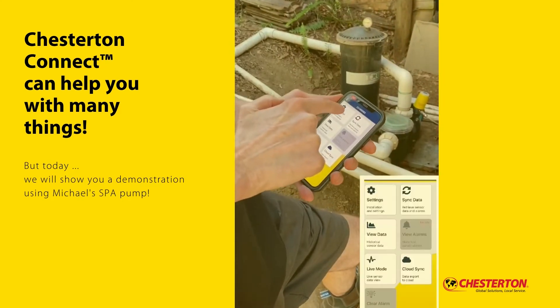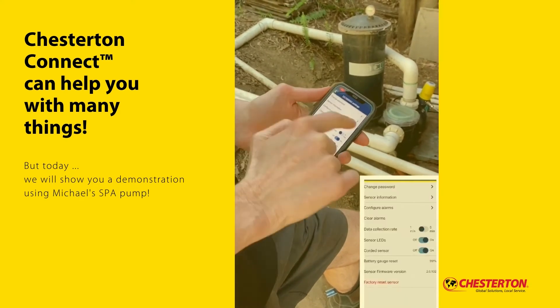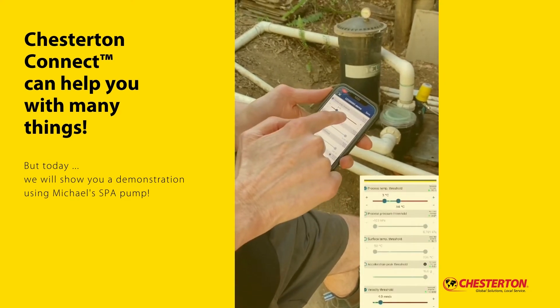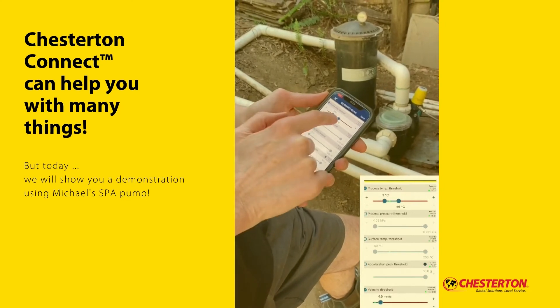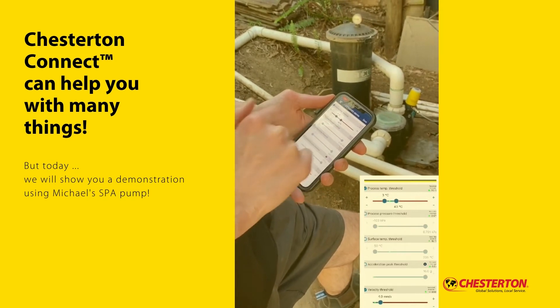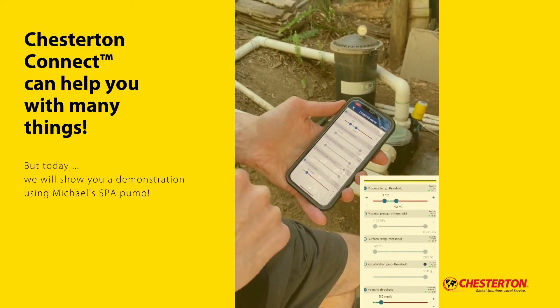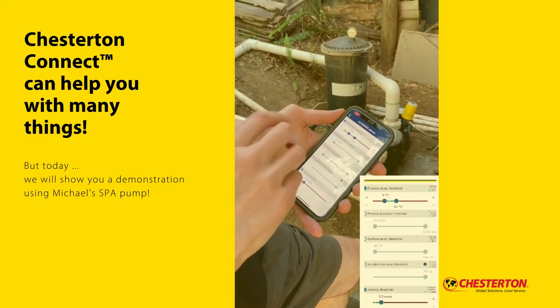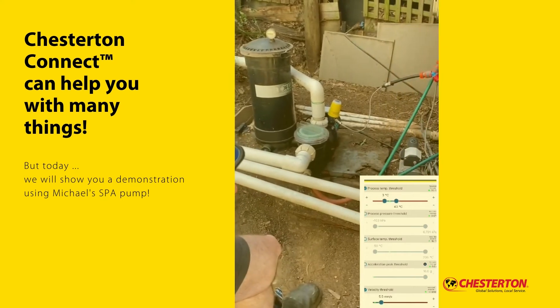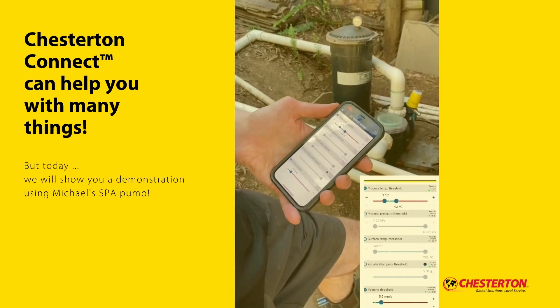I can also set up those thresholds. By going into the settings section, I can go on to configure alarms and set up where I want the temperature alarms to be — for example, when the spa is hot enough to jump in. 56 is a bit high, 30 is probably a bit low — somewhere around 43. I can also set some velocity thresholds to let me know if the bearings are starting to play up. I save that data and once the device registers these temperatures and vibrations, the light on top of the Chesterton Connector will turn red. It will also send me an email to tell me that an alarm has been reached.